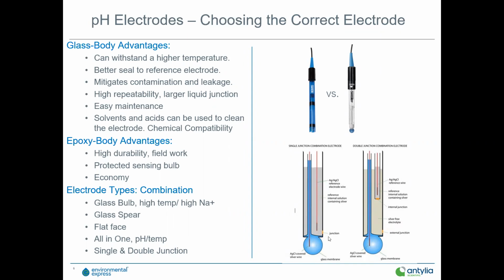The second one is poisoning. That's usually done by ions such as heavy metals, phosphates, sulfates, nitrates, amines, ammonia derivatives, and proteins. So to combat those solutions containing those poisoning ions, you want to upgrade to a double junction electrode. Now you'll see in the diagram on the lower right corner of this slide the double junction design. You've got your single junction here where the electrolyte is essentially leaking out, mixing with your sample, coming into contact with the glass bulb, making a measurement.